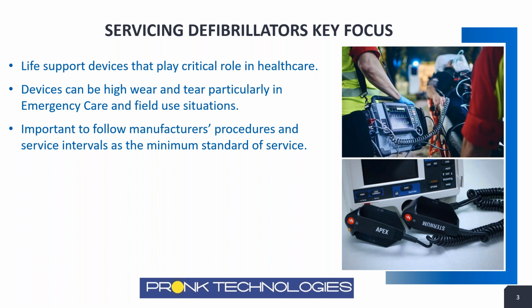So there's a lot of features within these devices. It's important that we understand what we should be testing when we're servicing them. The manufacturer's procedures are really detailed and helpful to understand what the important things are here. The service intervals, of course, are important too. Manufacturers will list in their service manuals the PM intervals or the service intervals for these devices, be it the device, or maybe the batteries themselves. It's important we follow those as a minimum standard. And depending on our facility and the application, you may want to consider even servicing them more frequently.